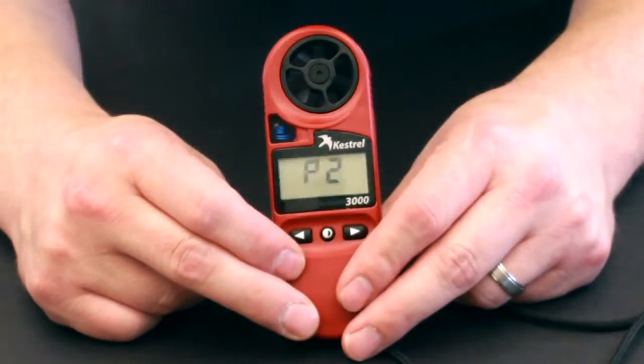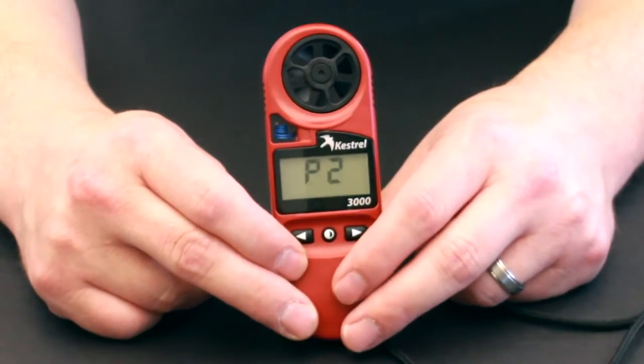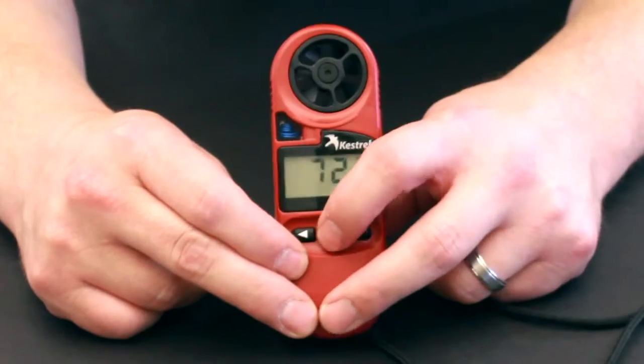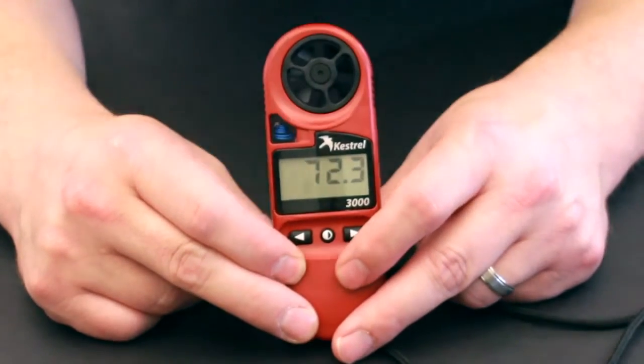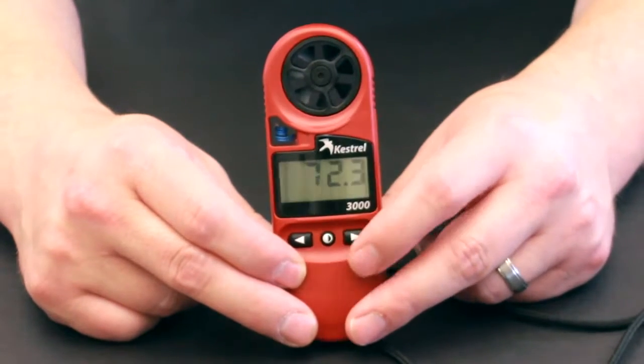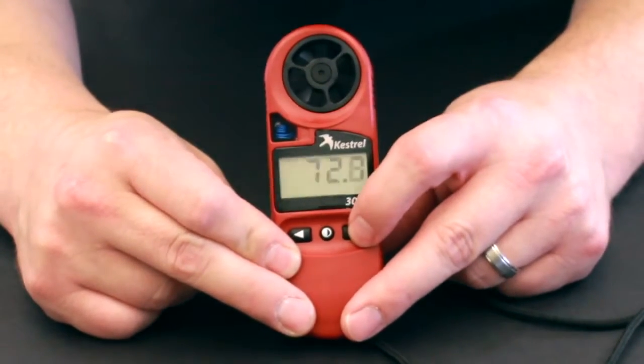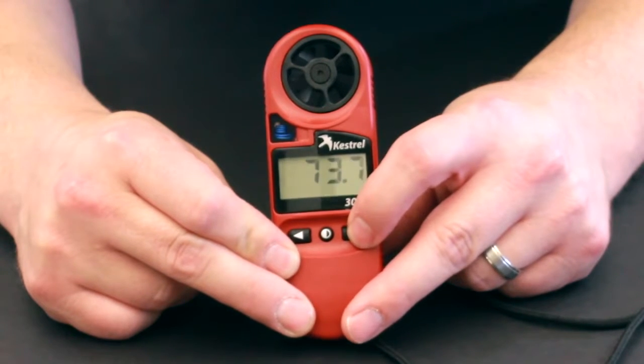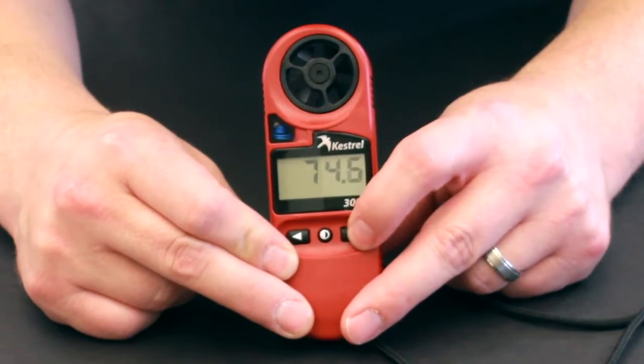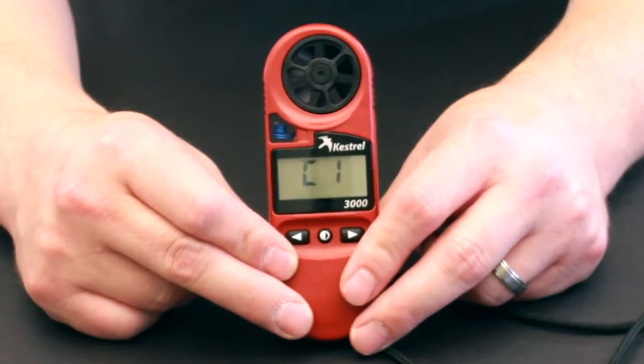Once we have that, we'll hit the center button to move to the second value which is P2. This is going to be the value of the sodium chloride chamber. So let's hit the center button and it says 72.3. We want this to be 75.3 as noted in the instructions, so let's increase this until we get the 75.3. Now we'll hit the center button. Now we're ready to start the humidity calibration.